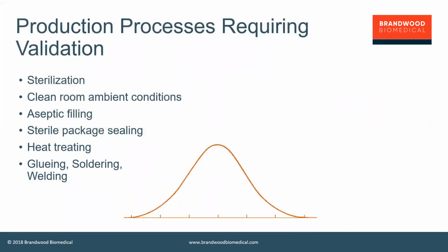But there are a number of processes where you can't do that. There's the concept of a special process, a production process which requires validation, and that is simply because you cannot make a measurement on the product without destroying the product. Examples of special processes, sterilization being one of them. You can only determine if an individual product is sterile by opening the packet and putting the product in a broth and seeing if you can grow anything, and that's then destroyed the product. Aseptic filling, the same. Sterile package sealing, you can only determine whether the package is properly sealed by attempting to open the seal. And treatments such as gluing, soldering, welding, or additive manufacturing, building up layers, you can only tell if that's been done properly by mechanically testing the device which is going to destroy it.